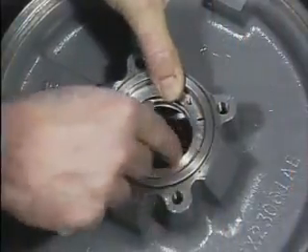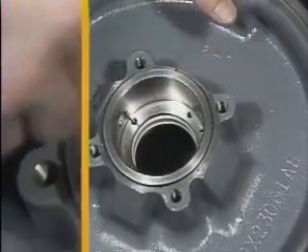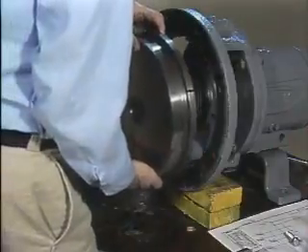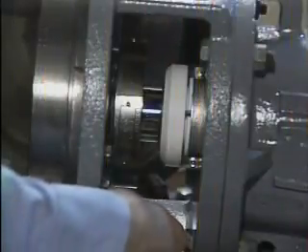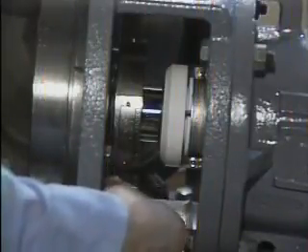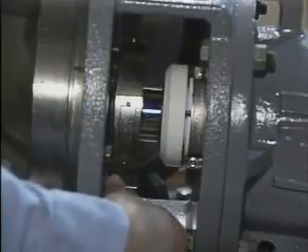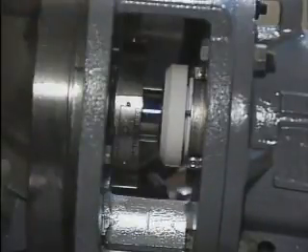Now the back plate is prepared for installation. First, the bushing is inserted into the stuffing box and secured with a screw. Then the back plate is installed on the pump frame. Next, the gland plate is slid into position, and the cap screws that hold it in place are tightened. Then a feeler gauge is used to measure the gap between the gland plate and the back plate, to make certain that the gland plate was tightened properly.